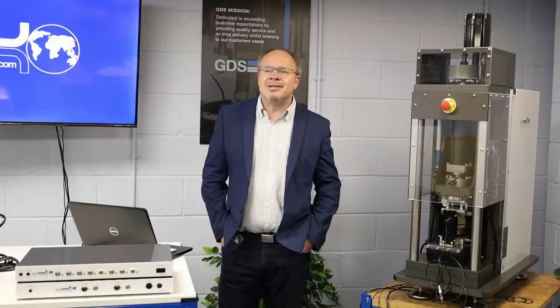Passive and active height control, which is a requirement of ASTM. CNS testing, constant normal stiffness, a very popular test now, specifically for offshore wind. Local strain, the addition of local strain transducers to measure directly on the specimen. Our unique shear load cell, which again measures directly on the specimen and removes any friction from the system from linear guides or ball screws. And the performance of the machine. For example, the machine can go to a frequency of 5 Hz with a double amplitude of 3.5 millimeters.